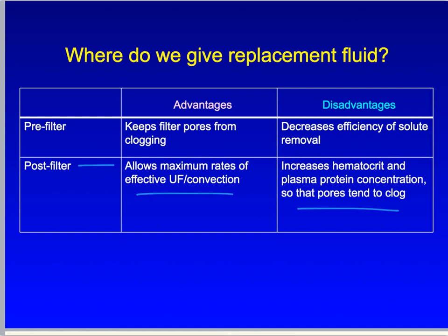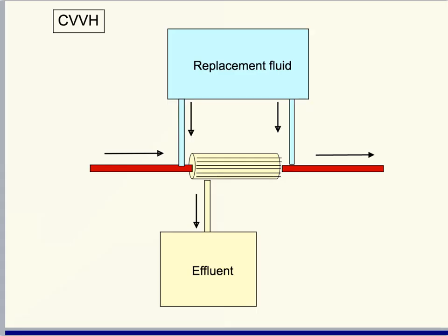On the other hand, infusing replacement fluid before the filter keeps the pores from clogging, but results in removing some of the fluid before it ever reaches the patient and diluting the concentrations of stuff to be removed before the fluid gets to the hemofilter. In some institutions, ours included, a mixture of pre-filter and post-filter replacement is used to avoid extremes of the pre- or post-filter problems just described.